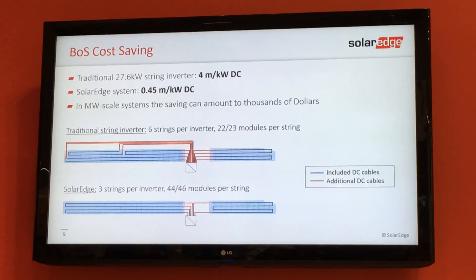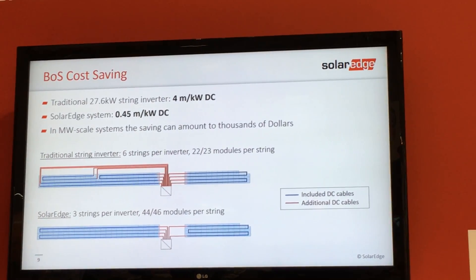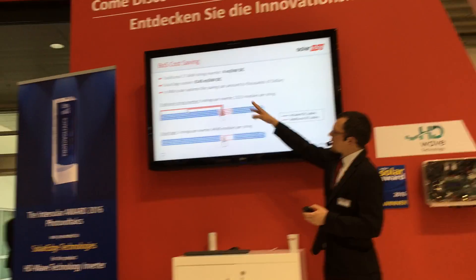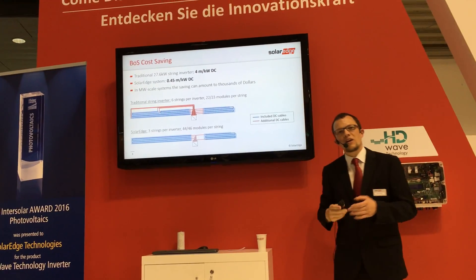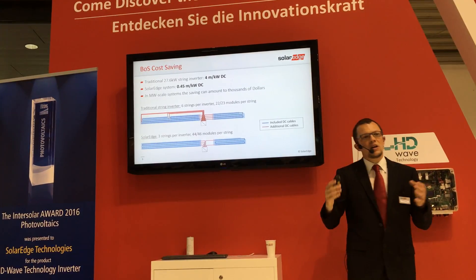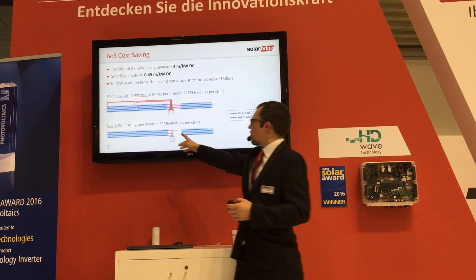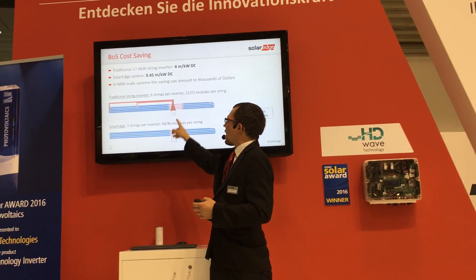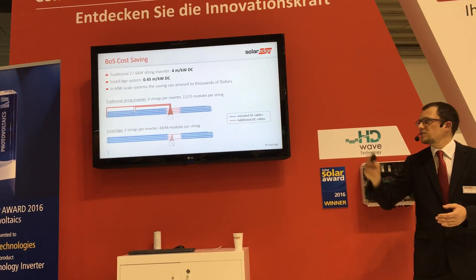The optimizers are DC to DC converters, so they can decrease the output voltage and increase the current. That way, we're able to put up to 11.25 kilowatts in one string. For this same 27.6 kilowatt inverter example, with the SolarEdge system we only need three strings to connect all the modules — up to 44 or 46 modules in one string. That gives you quite a good amount of savings on the cabling. With SolarEdge, we only need this additional cabling, whereas with the traditional inverter you need to run all these red wires to connect the different strings to the inverter.